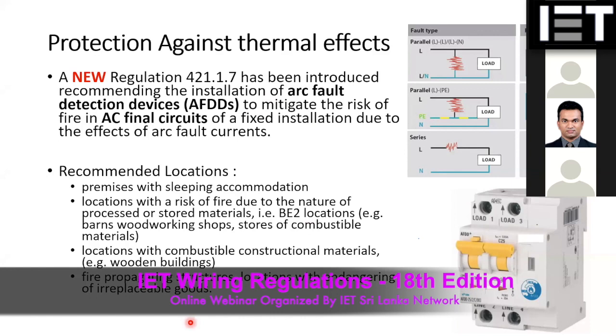So for the regulation, normally we tell people to go with circuit breakers and RCDs, but now there is a new requirement. You have to evaluate whether there is a risk of arc and what type of location it is, and if the location belongs to this type of location, then you have to go with arc fault detection.